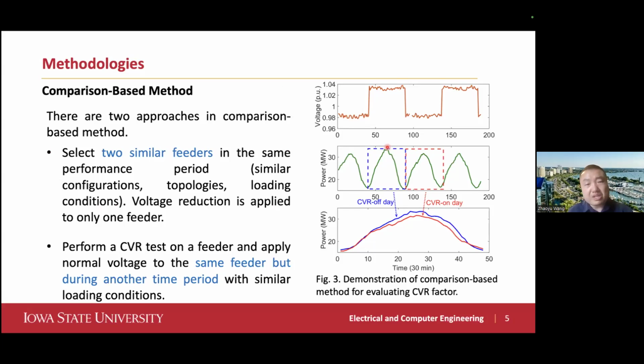You select two similar feeders during the same performance period, apply voltage reduction to one feeder and regular voltage to the other, then calculate the difference in power consumption. Another approach is to select one feeder, apply normal voltage for a period of time, then apply reduced voltage for another period, and calculate the difference in consumption.